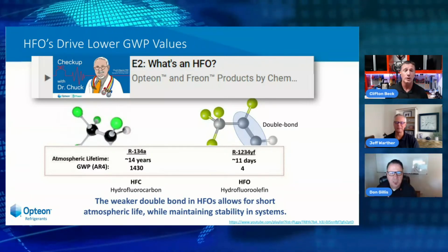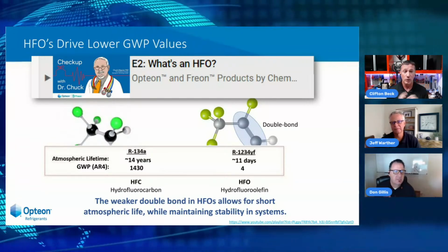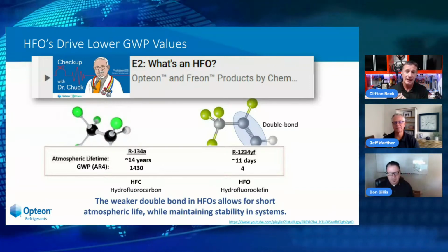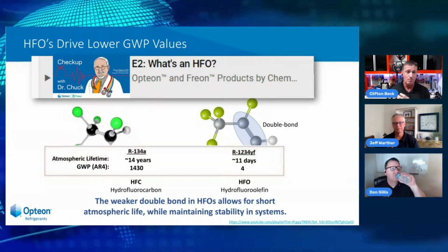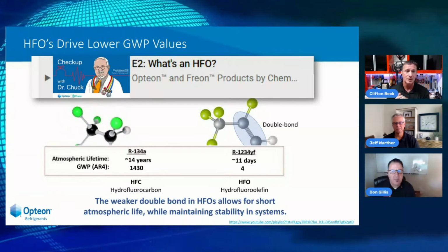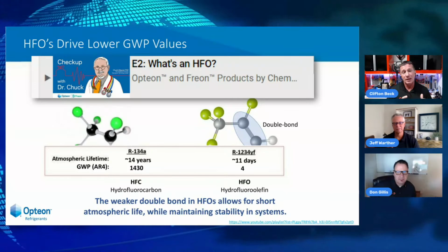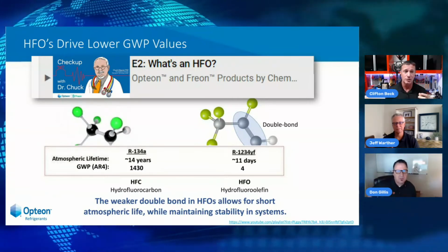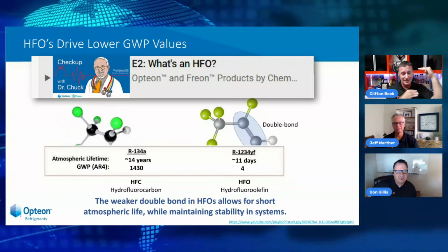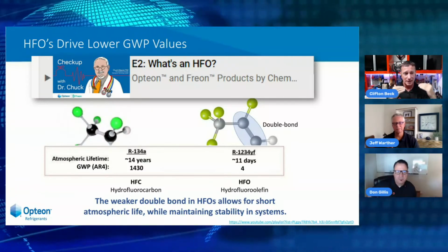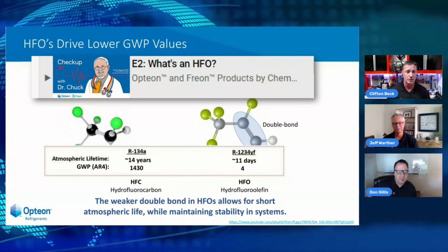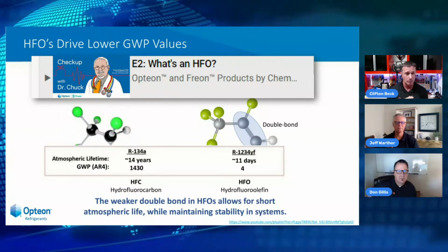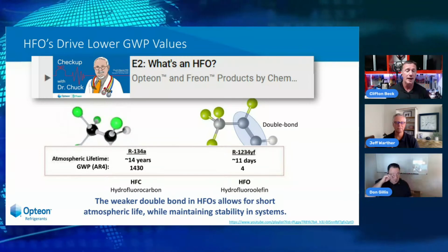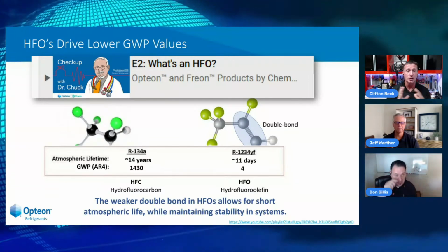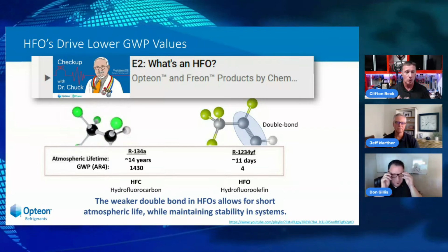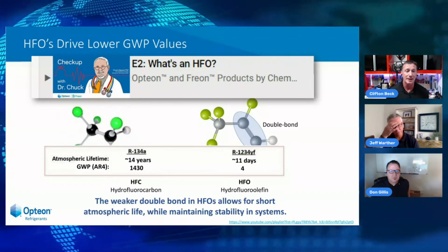That's a really interesting point. When we talk about the HFO, we really are talking about a synthetically modified HFC that has a different bond on our carbon-based atoms. We're using that olefin base or an alkene base, which does that double bonding of the refrigerant that allows it to break up faster as it enters the atmosphere. That's the reason we have that lower GWP for our refrigerant. It's very stable at lower atmospheric and under-pressure conditions, and as we introduce it into higher atmospheres, it is easy to break down. So its longevity has been significantly reduced over our HFC refrigerants that we've seen in the past.